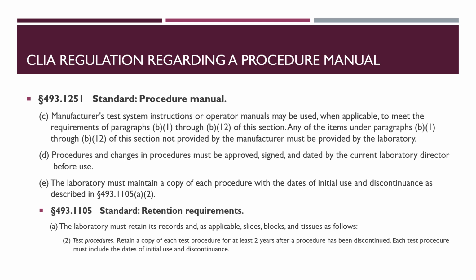In addition, CLIA also states retention requirements. So for anything that you might test, there are certain things that have to be retained for a set amount of time. Some things may be indefinitely, some things may be just a couple of years. And so any records that may be pertaining to that test, most things are about 2 years. There are some things that are a little bit longer, but this is also something that's going to be put in your laboratory procedure manual.